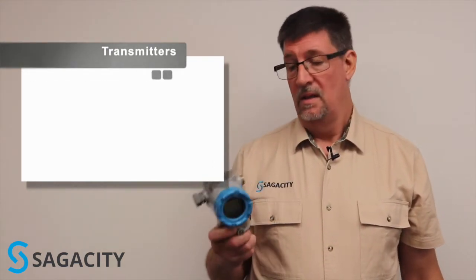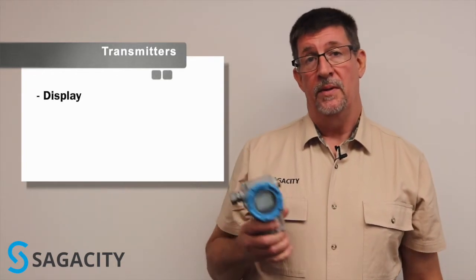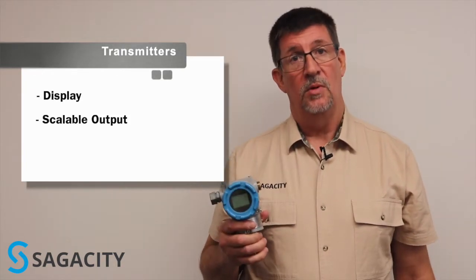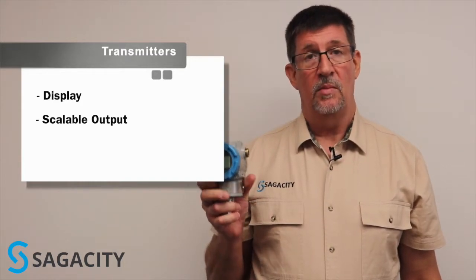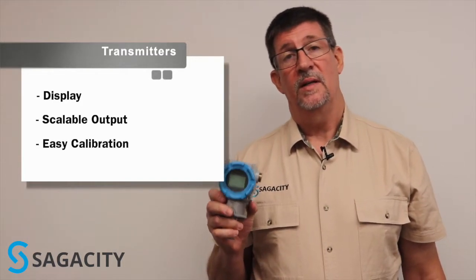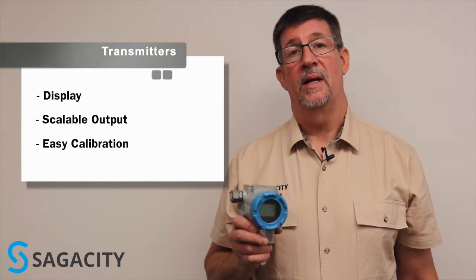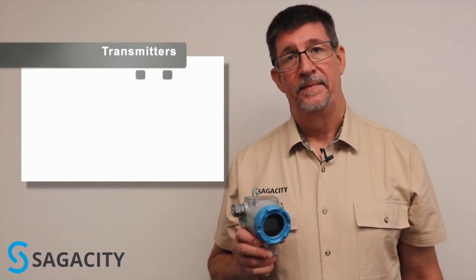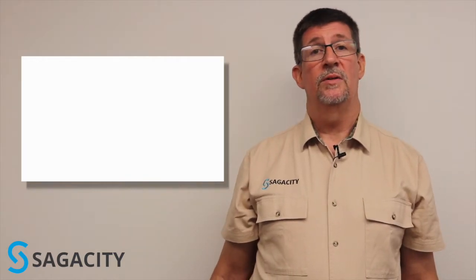Transmitters, on the other hand, typically have a display. Their output is scalable over a range and you can recalibrate these in the field typically pretty easily, versus recalibrating a transducer in the field. We're using an electronic device to measure pressure, but you need to make sure you use a transducer in the right spot and a transmitter in the right spot.